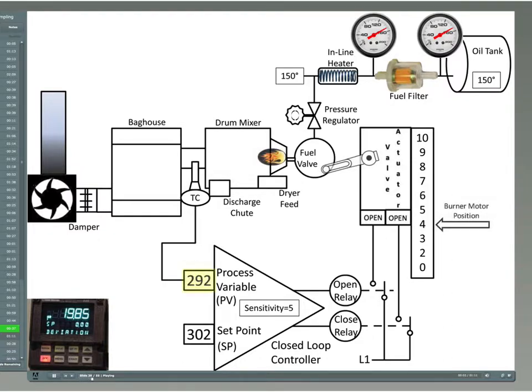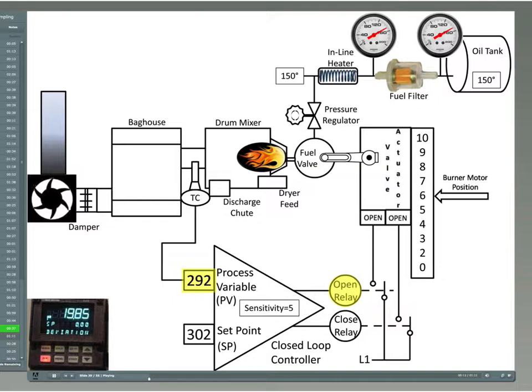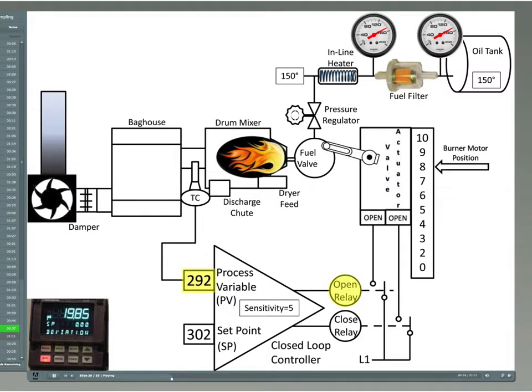The burner control is set to automatic and controls smoothly until the thin temperature probe fails. During a hot stop, the failed thin temperature probe is replaced with a thick, massive temperature probe. Since the replacement temperature probe responds more slowly to temperature changes, the controller is now hunting for its set point by opening and closing the burner position actuator too slowly.